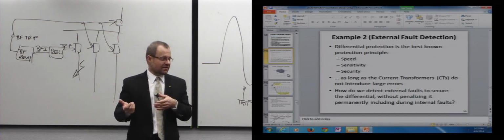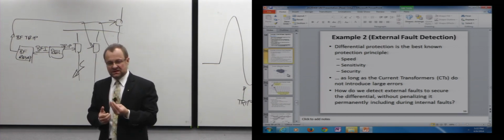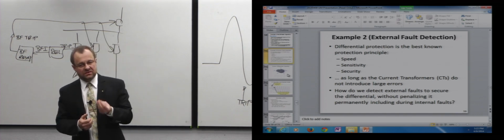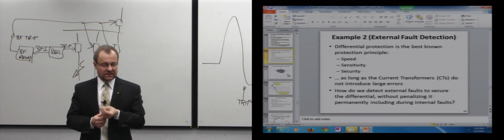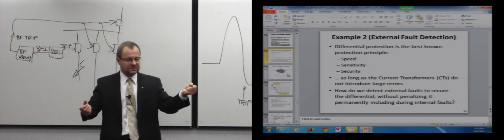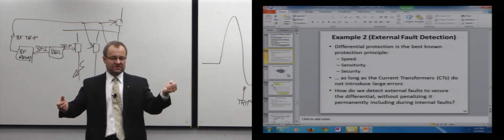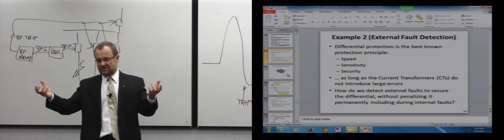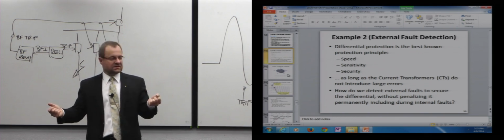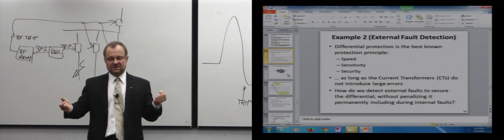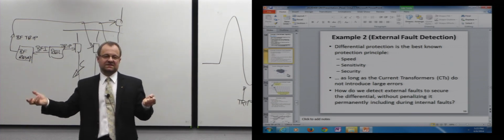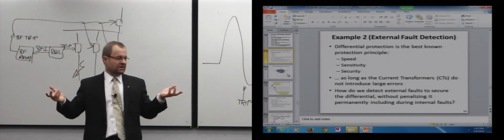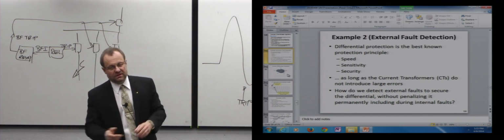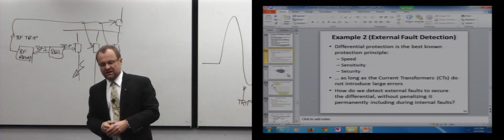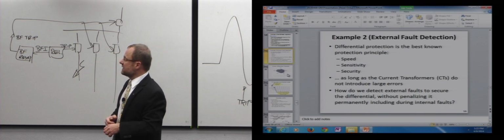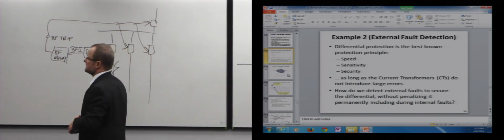We measure the secondary currents, right? So if the CT is lying to us, it's saturated, it will create a spurious differential signal, right? So we have two connections. One is 10 kiloamps, the other is minus 10 kiloamps. They sum up to zero. It's an external fault. But one CT tells us it's 10 kiloamps, and the other CT is saturated and says it's minus 8. We sum them up and we say it's 2 kiloamps. It's not zero. We should trip, right? There are different ways to deal with it, but one way that is very attractive in new relays is the external fault detection.